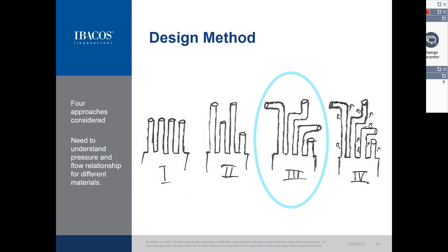So to briefly go through this proposed design method, we've got some of the steps listed here. At a basic level, this design method that we're proposing would start out with a standard load calculation. So you still have to know how much energy is needed by each room to maintain comfort at those peak load conditions. So you still have to do a manual J-type calculation. You would need to do a duct layout for the home run system to understand the rough lengths and the number of elbows, and those values are then used to understand the air that each duct is able to deliver.